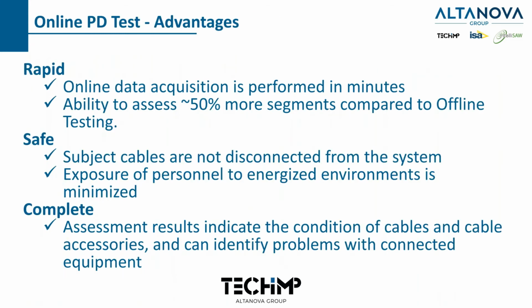Okay, so the testing is very, very rapid. Because it's done online, we don't have to disconnect. The advantage is we can do much more testing per day than offline testing. It's also very safe. We always get the question, is it safe? Yes, it is. We've been doing this for 20 years, and I have never had an incident. All of our technicians have the proper PPE. I'm going to show you how the sensors are applied. They're applied with a hot stick, so it's very safe.